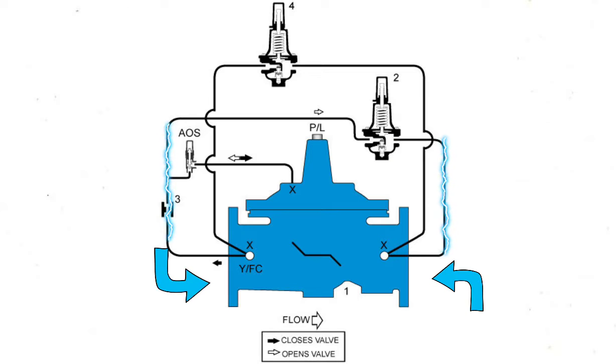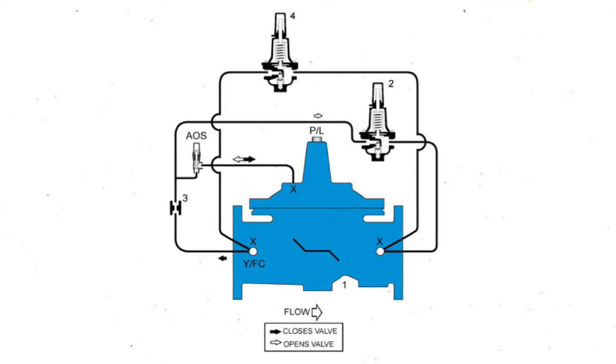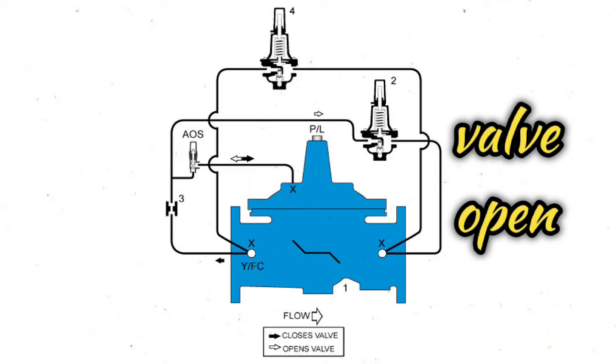When pressure on both sides of the main valve piston is equal, a spring located on the top of the piston acts as a differential force and closes the main valve piston. As pressure against the bottom of the piston increases and exceeds the pressure exerted against the top of the piston plus the force of the spring, the spring tension is overcome and the valve opens.